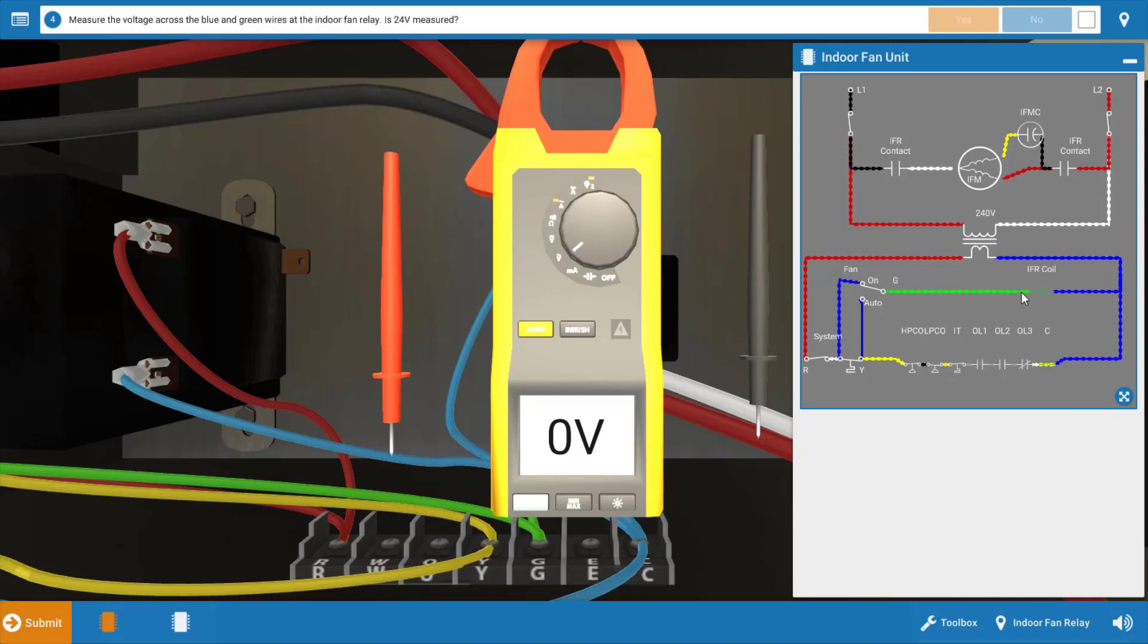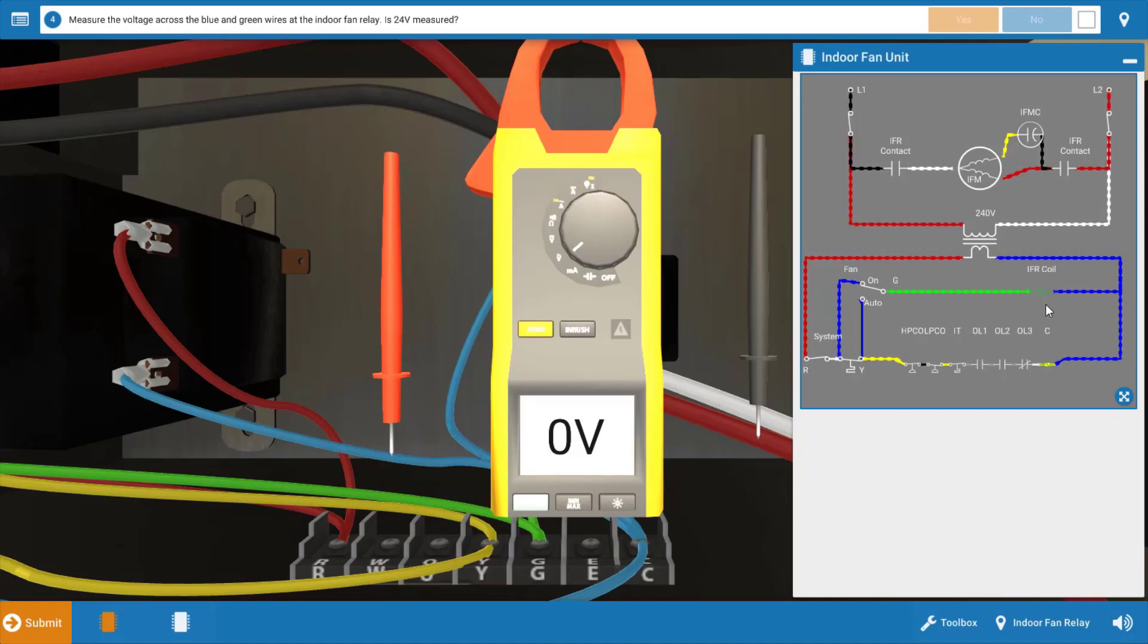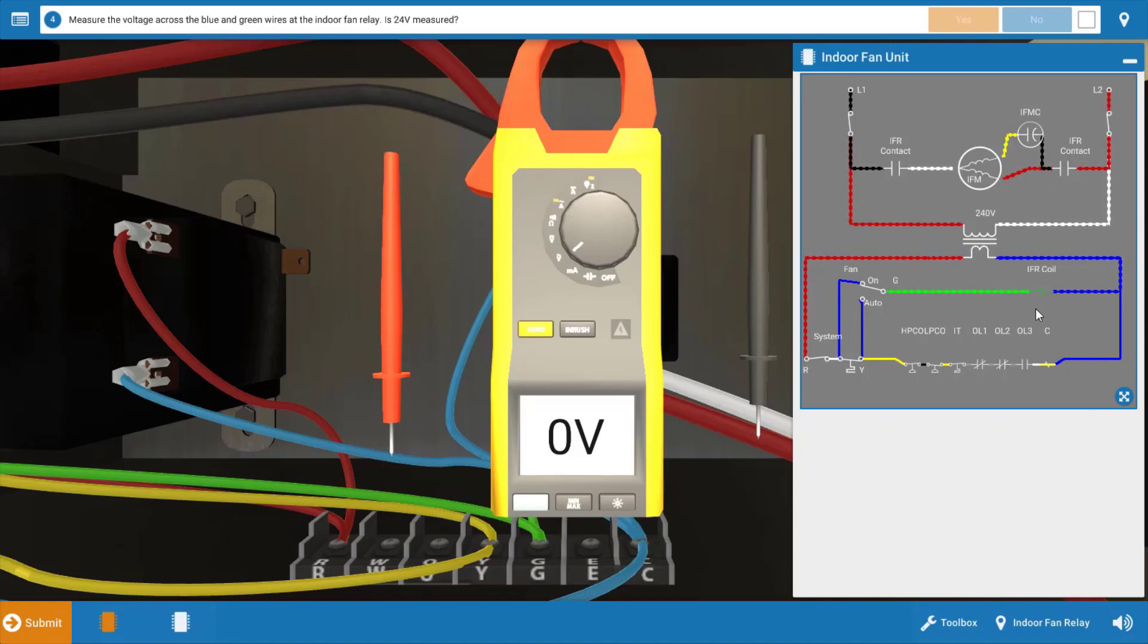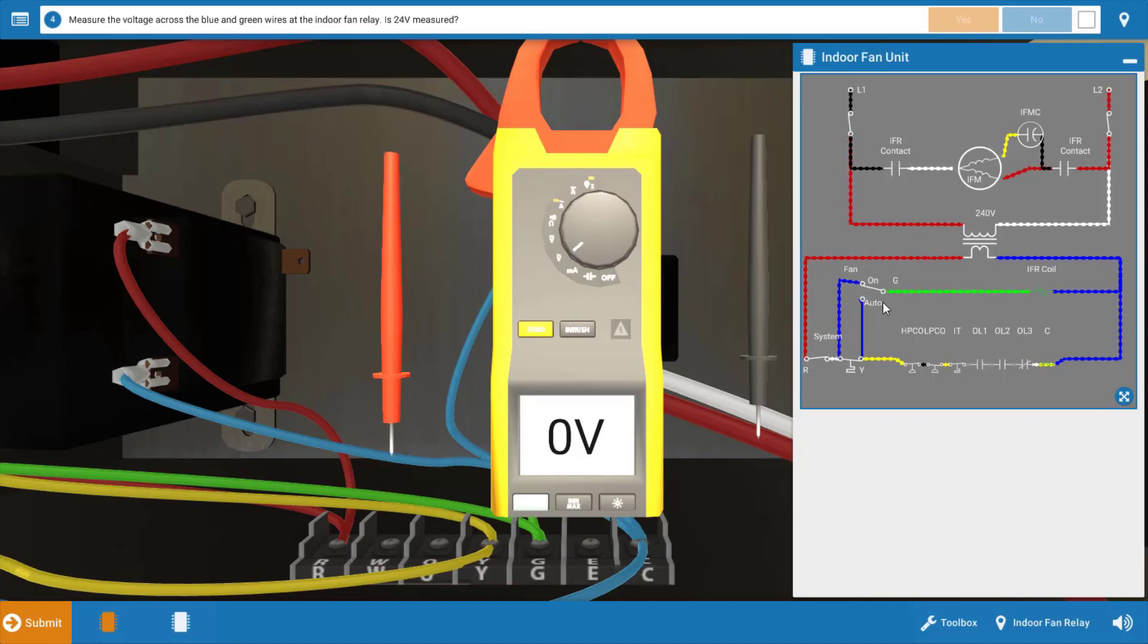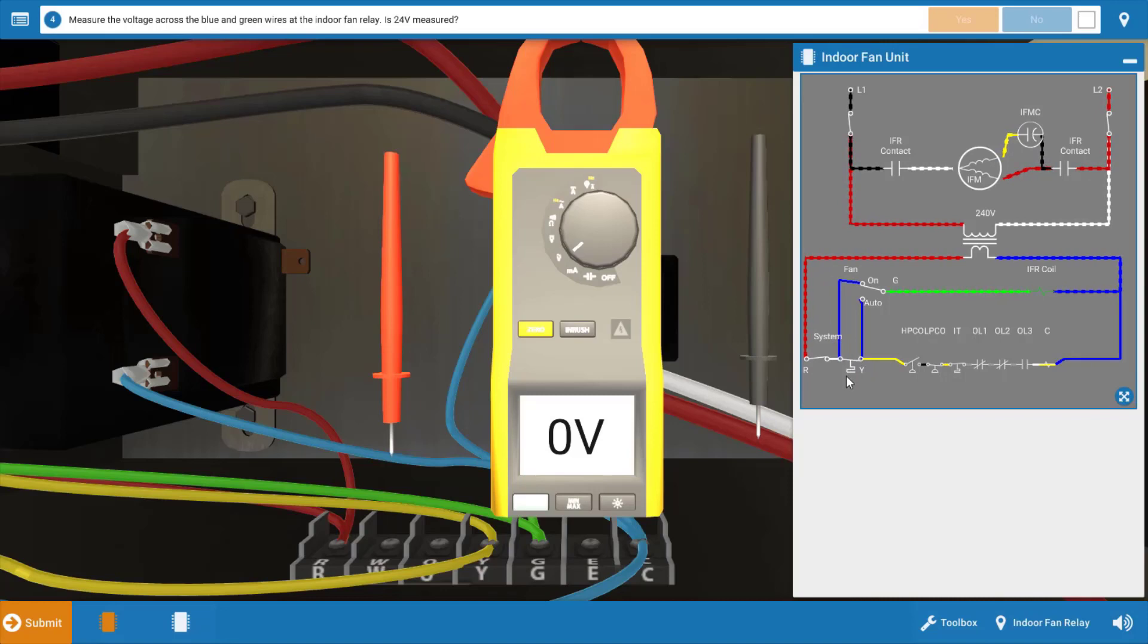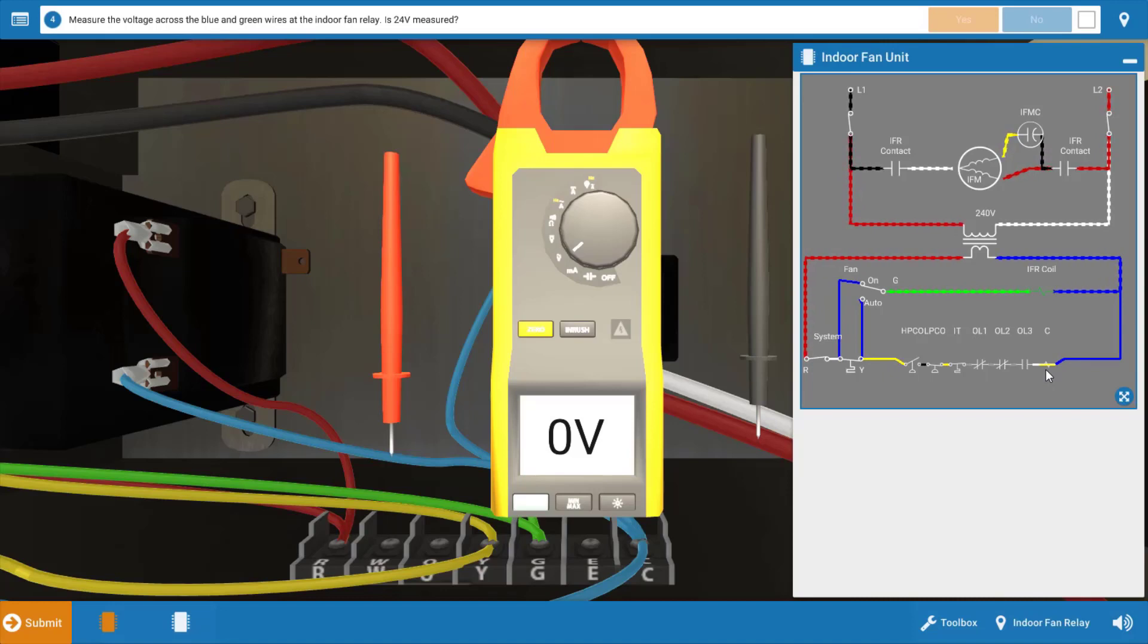In the low voltage circuit, it's possible that we have a faulty indoor fan relay coil, which if that's faulty, it's not going to pull the contacts in and provide 240 volts to the motor. And it's also a possibility that our thermostat is faulty, meaning the fan switch portion of the thermostat is faulty. The fan switch sends 24 volts out of the G terminal to the indoor fan relay coil. We know that the cooling contacts closed because the contactor is obviously energized due to the fact that the outdoor unit is on.